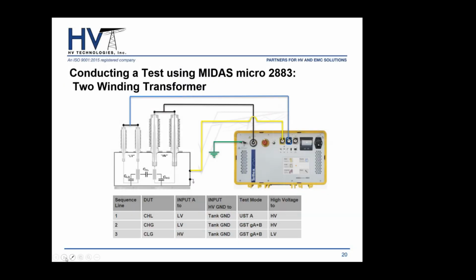So for a two winding transformer, if we want to do the high to low voltage capacitance and tan delta, we'll connect our high voltage lead, the black line right here, to our high voltage, our measuring cable to our low voltage, our high voltage ground to the tank, and then of course the safety ground. And we'll choose UST, and since we chose the measurement channel A, we'll do UST-A, and that'll give you your measurement for the high to low voltage.